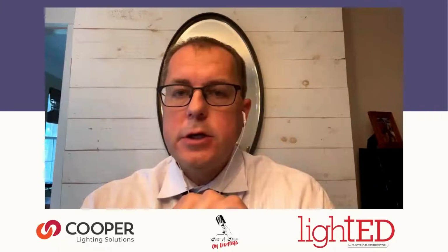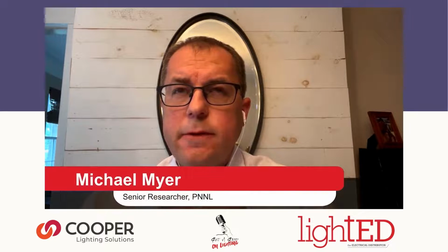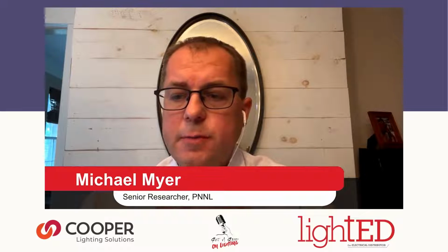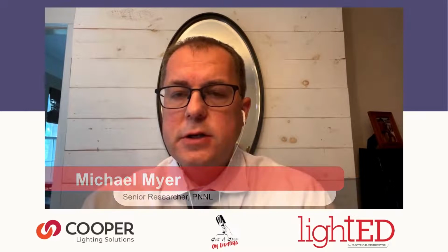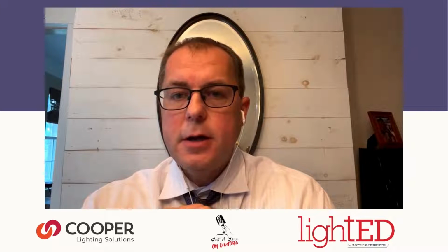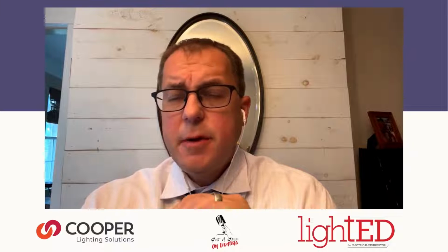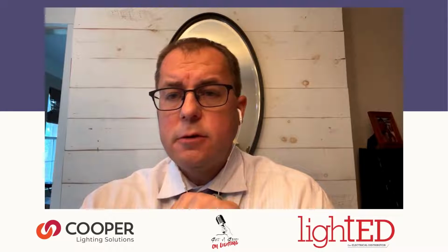Michael, you want to expand? We recently completed a project with the U.S. Department of Defense, Tinker Air Force Base. There, the lighting system was in both an industrial high bay space as well as about 5,000 square feet of office. Exactly as Axel said, when the granular sensors didn't detect any occupancy, there was a drift in the temperature for some setback, as well as some fans. That saved about 38% of the energy from the mechanical system.